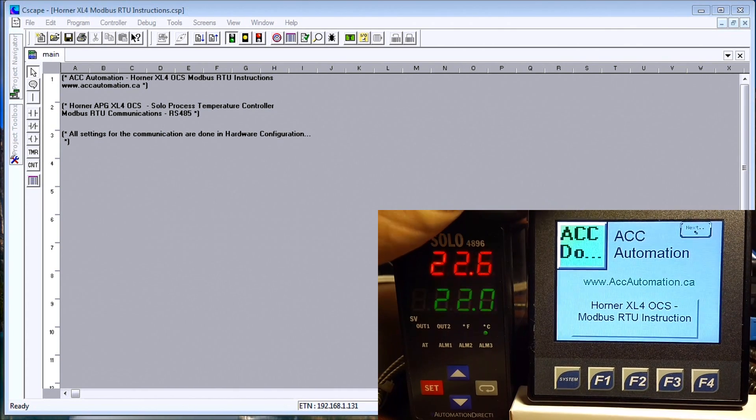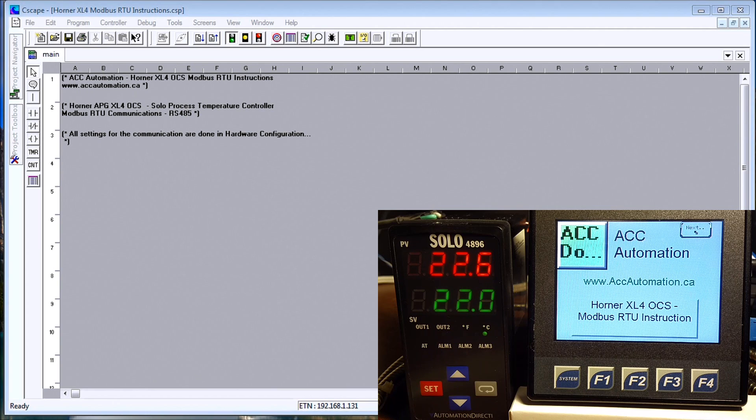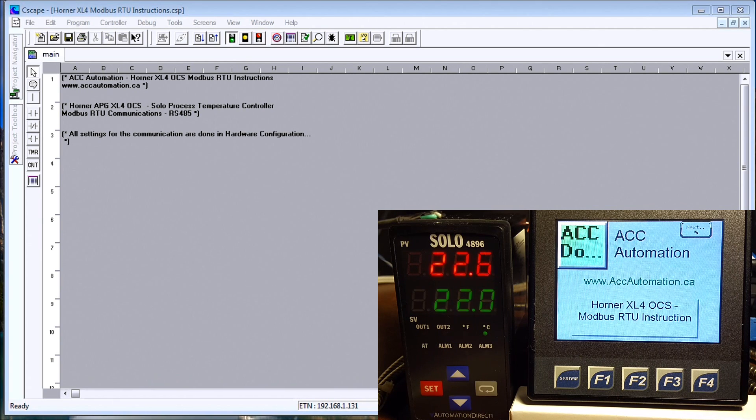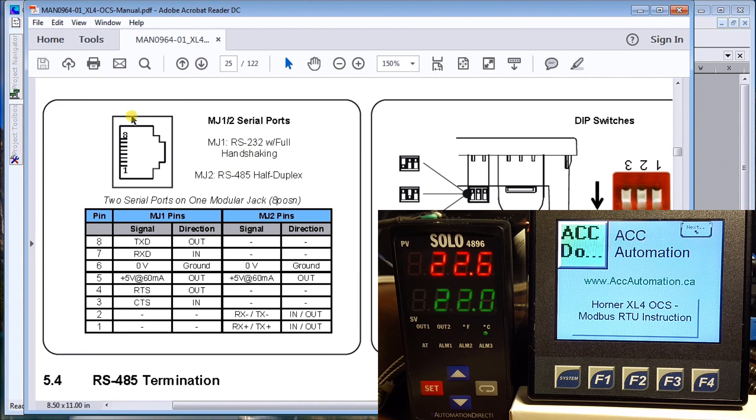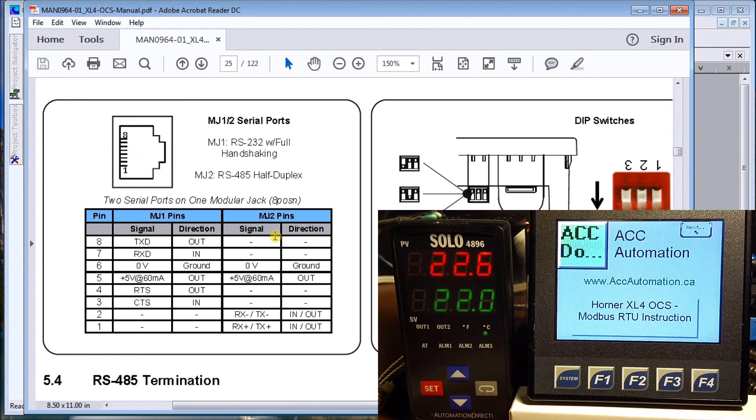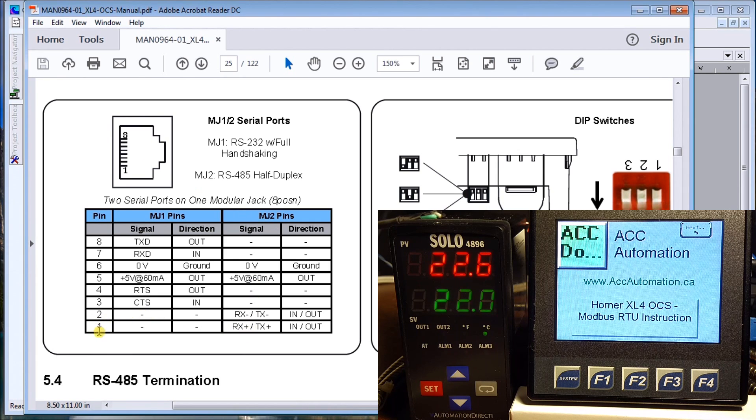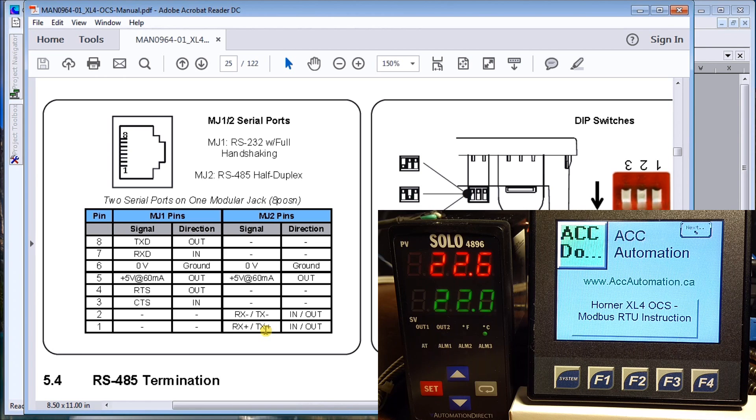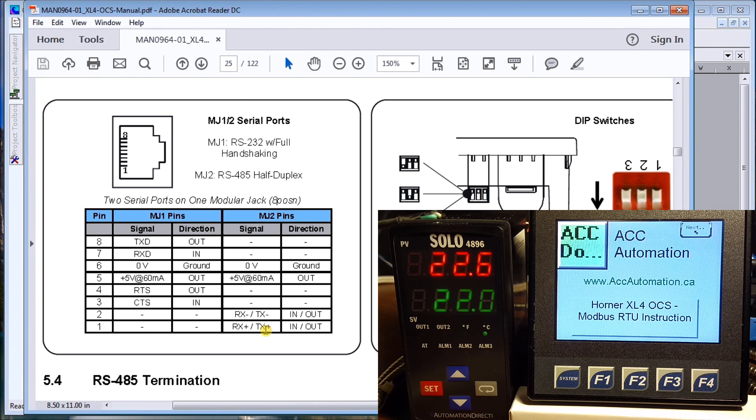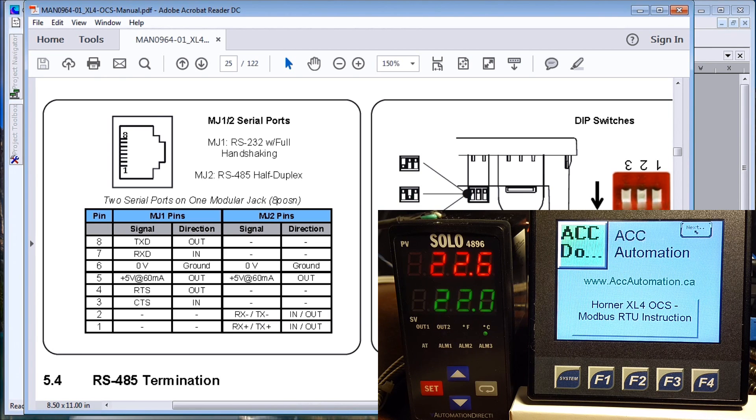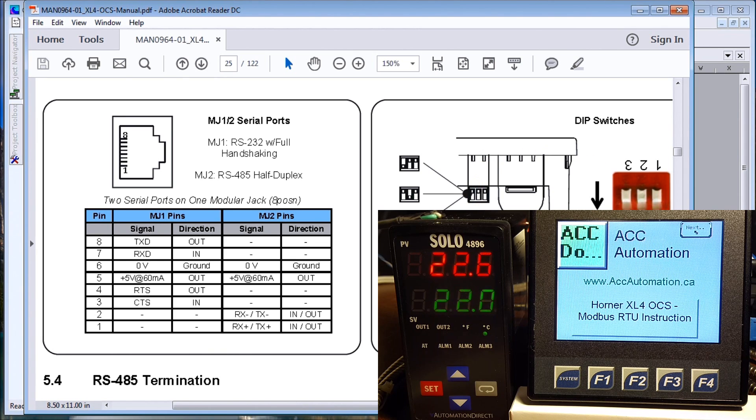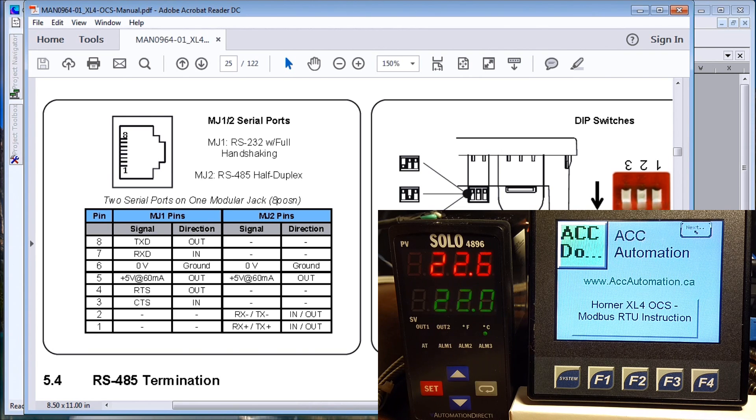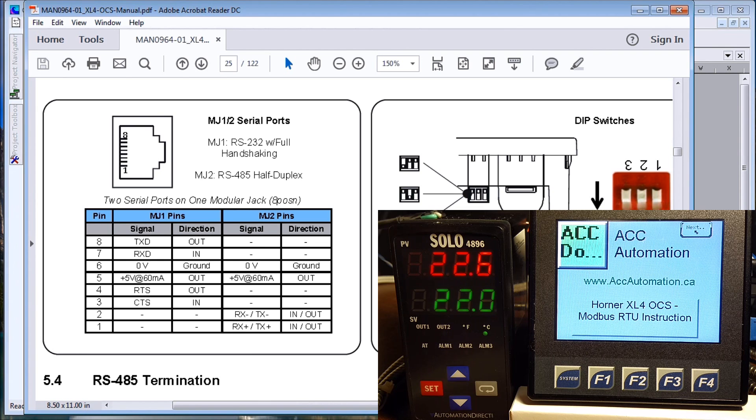If we call up our manual, you will see that this is the RJ45 port, and what we'll be using is pin number one and two, which is our transmit/receive on our RS-485 communication. There's also some switch settings which correspond to the termination if you need it on or off. In our case here, because we're such a short distance between the two units, we don't use that at all.